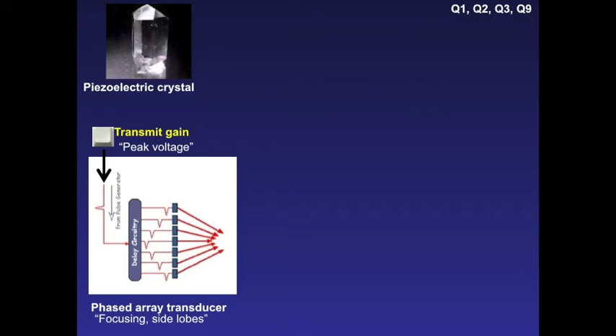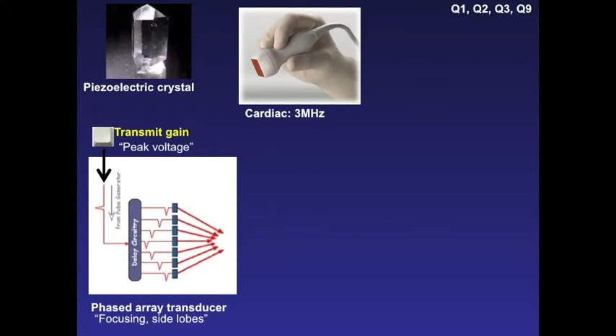Now, I'm talking about a phased array transducer. There were mechanical array transducers, which was one single crystal that was moved and took images as it moved. So the transmit gain, one of the knobs on your standard echo machine, but not on your pocket-sized devices, the transmit gain increases the voltage, rings the bell harder, and therefore gets a brighter image simply because it emits a more powerful signal.